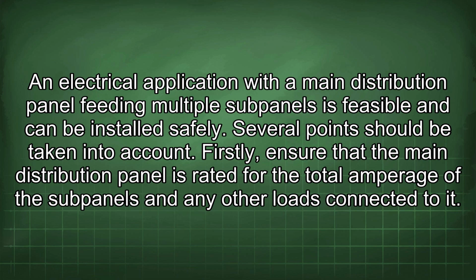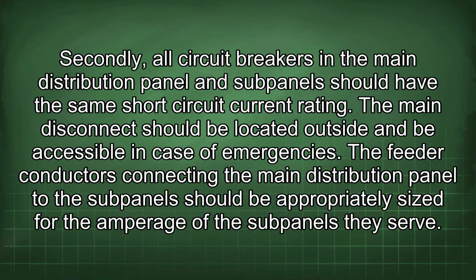Several points should be taken into account. Firstly, ensure that the main distribution panel is rated for the total amperage of the subpanels and any other loads connected to it. Secondly, all circuit breakers in the main distribution panel and subpanel should have the same short circuit current rating. The main disconnect should be located outside and be accessible in case of emergencies.